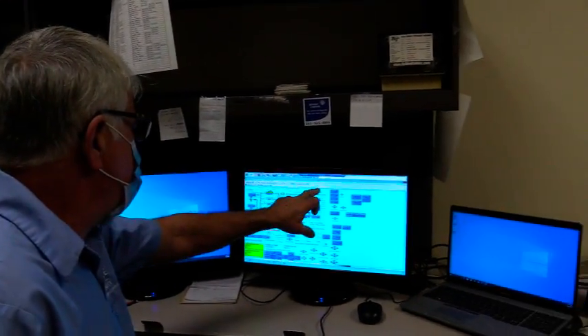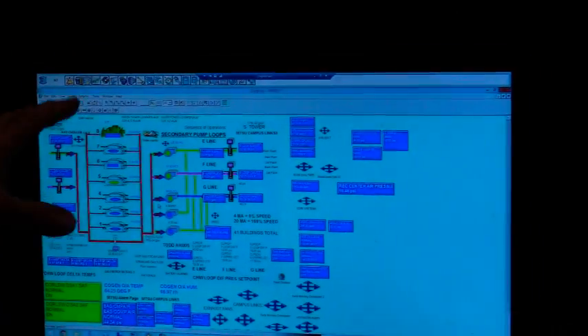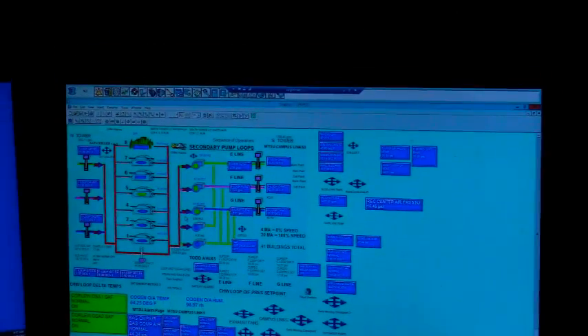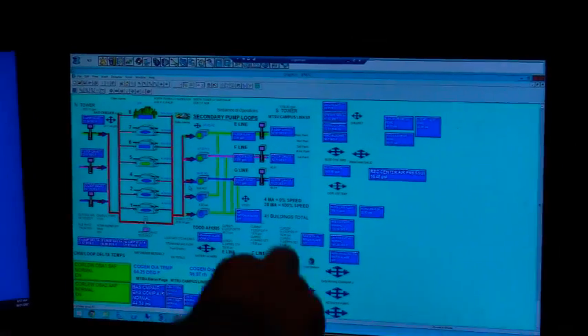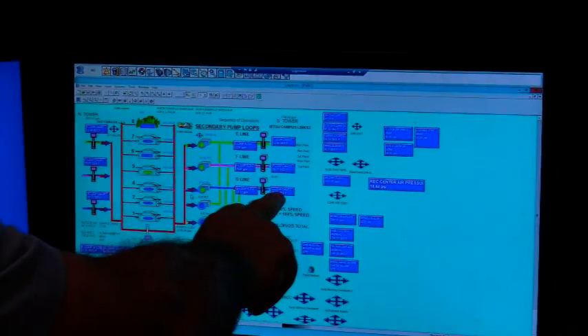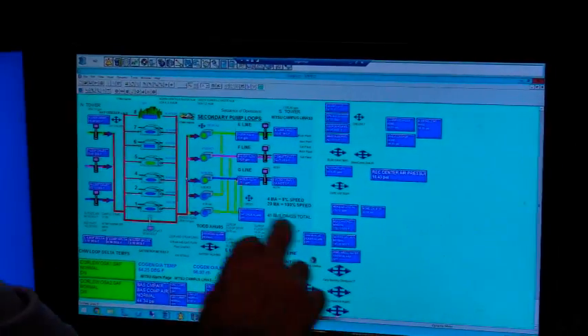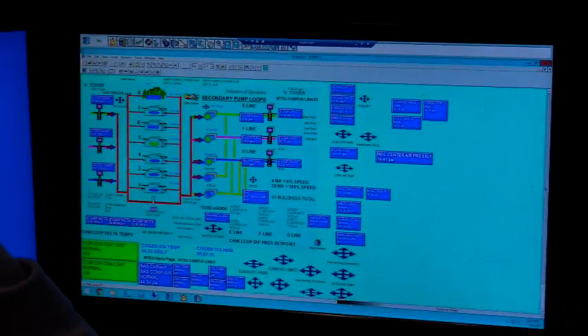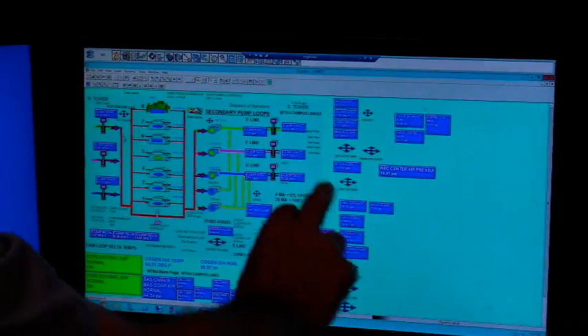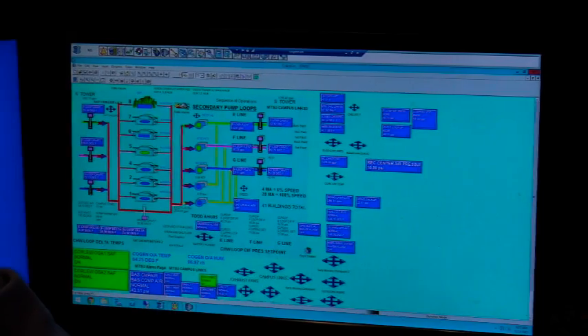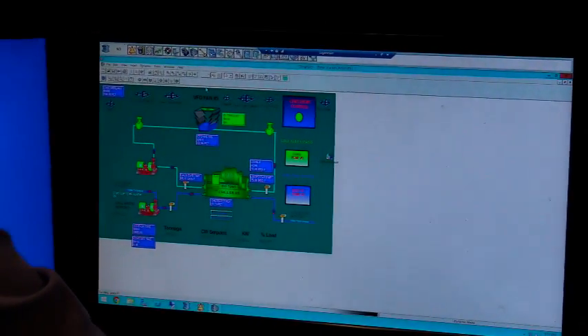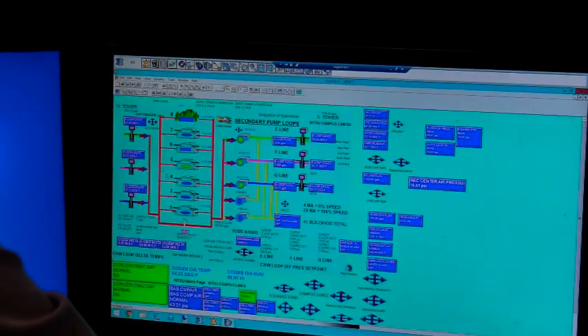Okay, I go to the PMP2 page, and that gives me my chillers. When I check them, the first thing I do is check my temperature. Right now my temperatures are real high. I should be around 42, but I'm at 52 right now. And I'm loaded up to the max, so I need to start up another chiller.